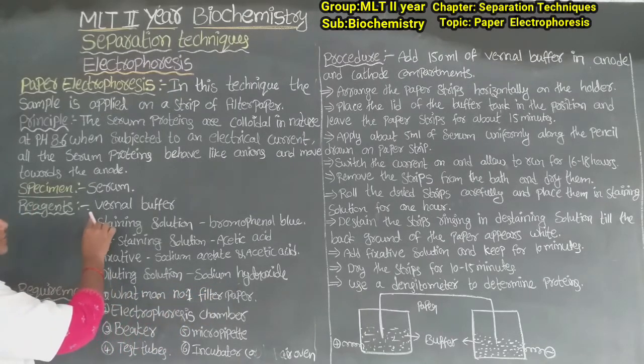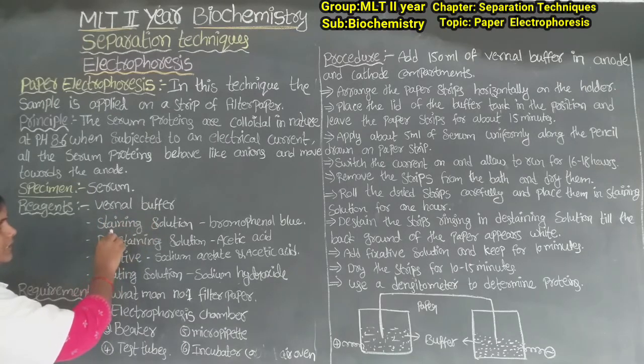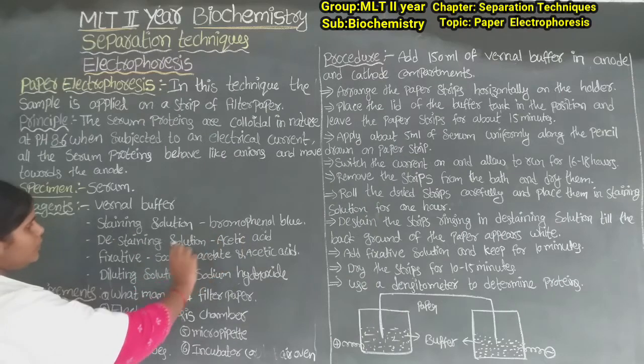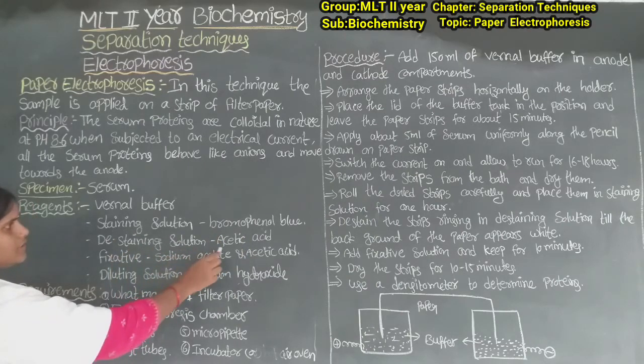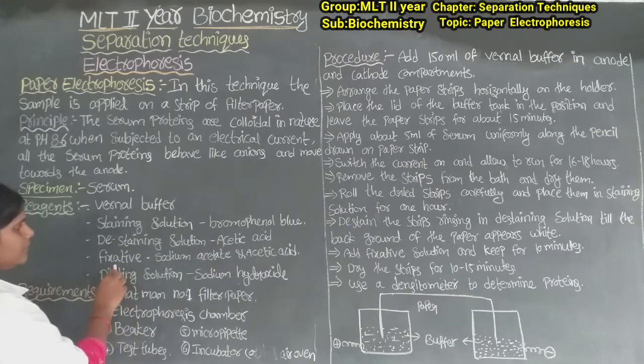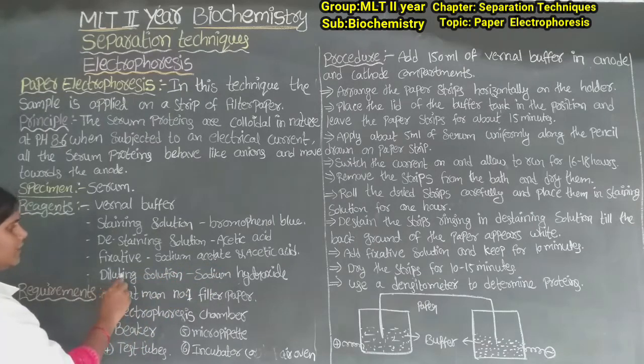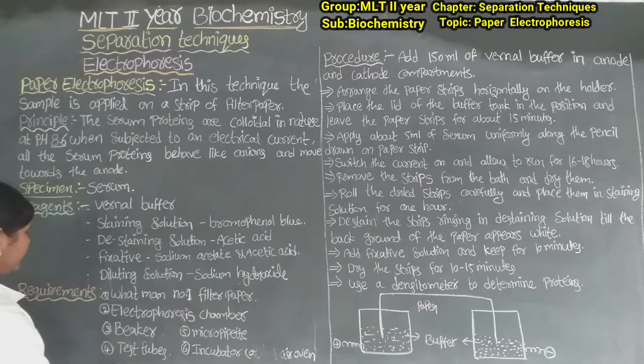The reagents are: first, veronal buffer; staining solution — bromophenol blue; de-staining solution — acetic acid; fixative — sodium acetate and acetic acid; and diluting solution — sodium hydroxide.